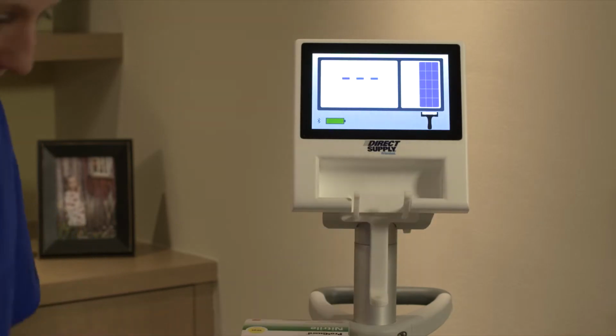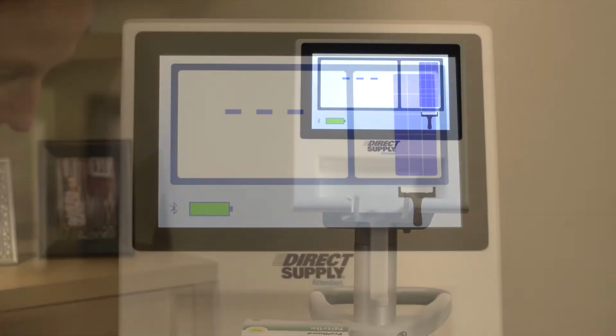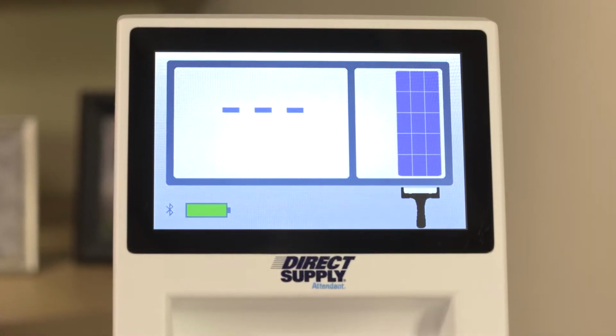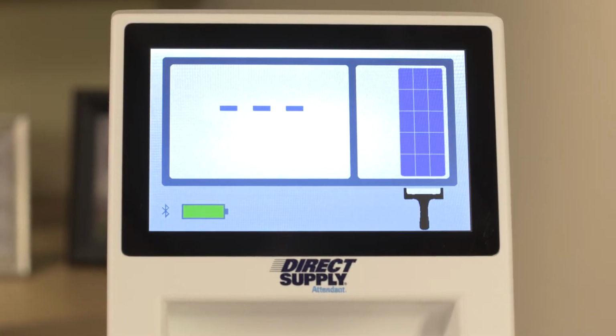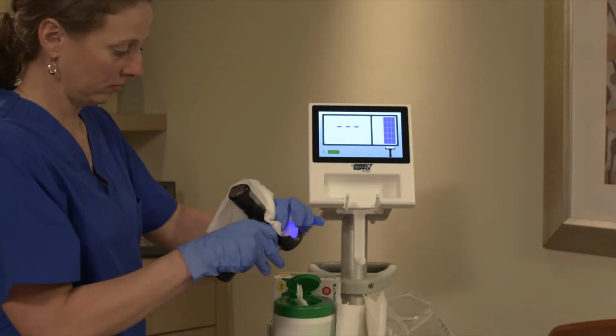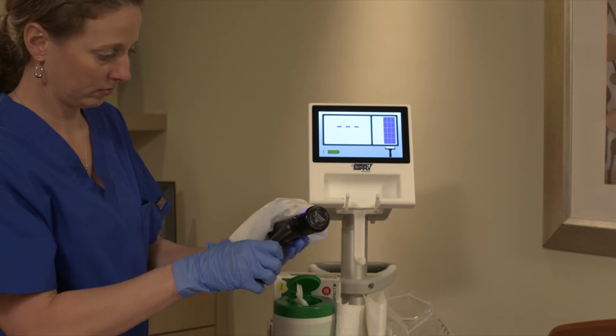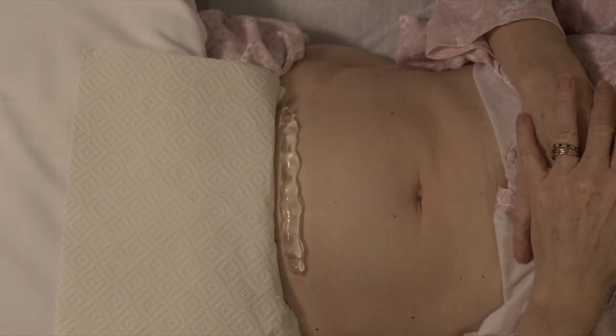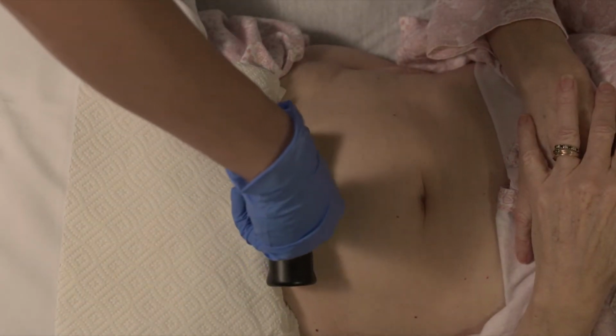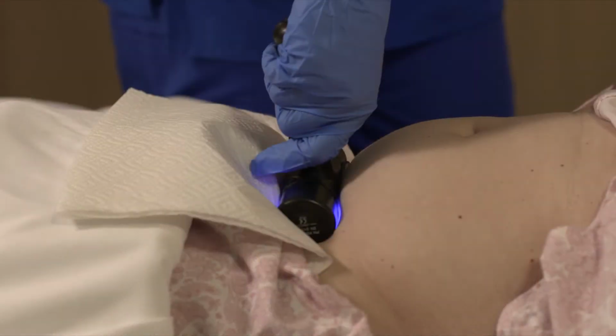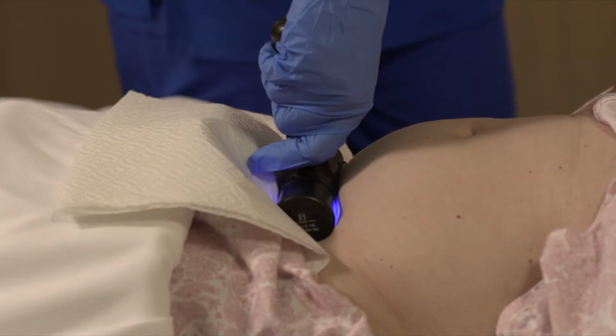Remove the scanner probe from the console to wake up the system. Blue lights will appear in the scanner probe window, indicating it's communicating with the console. Wipe down the scanner probe if needed before proceeding. The scanner should be placed midway between the pubic bone and navel of the resident. The handle should be pointing straight up and down.